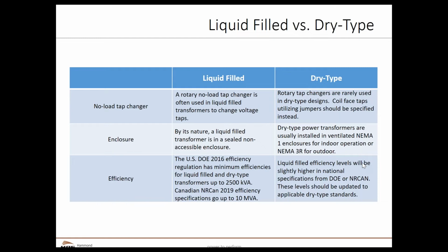And by twisting a dial with a wrench or something like that, I can change the taps within the liquid. And there's some advantages to doing this. I can do this relatively inexpensively and easily because I'm not worried about arcing, where I would be if the switch was just in air. And I also don't have to pull all those taps out with additional bushings through the transformer. So there are fewer points where that transformer can leak. Okay, this is not a bad solution for a liquid filled transformer.